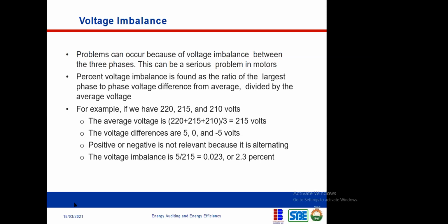What this simply means is that if you have a three-phase system, for example, you have 220 volts, you have 215 volts, you have 210 volts. Now this is a three-phase system, right? They are all operating at different voltages, 220, 215, 210. And mind you, this is powering one piece of equipment, perhaps a three-phase motor. Because they are not all on the same voltage, there's an imbalance between them. So how do we calculate the level of imbalance between these three voltages? That's what voltage imbalance is all about, and I'm going to explain how we can calculate that.